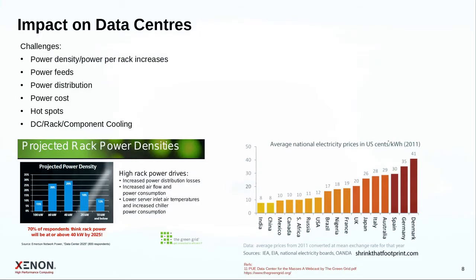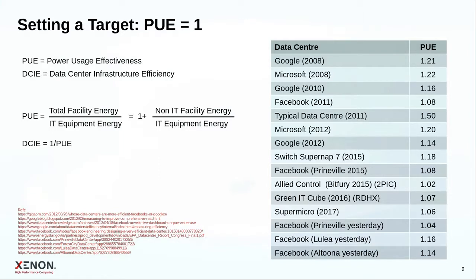So how can we quantify where we're at and what we want to achieve? A very commonly used metric is PUE, the power usage effectiveness, calculated as the ratio between the total facility energy - essentially all the power that goes into an HPC center - divided by the energy that's really used by the IT equipment itself. So looking at the ratio between the non-IT facility energy versus the IT energy is really what I'm interested in: how much energy do I need to actually keep my systems running. That includes all the overhead of the systems, including power conversion losses and cooling.